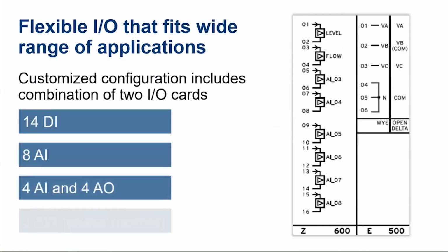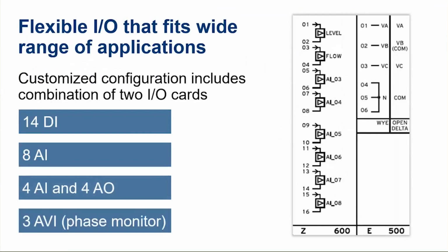Now you've still got two cards that you can use in slots Z and E of the unit, and those you can configure to be several different options. What we have up on the screen right now is some options that we see a lot of customers choosing. You have the analog input card that has the level and the flow meter input. That's typically what a customer will choose if they've got a level transducer, a flow meter, or maybe a water pressure sensor that they want to bring back because they have a water and wastewater system and they want more visibility in the field. Any of those can come into those analog input cards, as well as current transducers to see how much current the motor is pulling, and be brought back to either be viewed on the SCADA system, or you can add logic in the controller to make good decisions on what the controller should do if it sees changes in current or a bad level or flow. This other card to the far right on the slide, in slot E, is our phase monitoring card.